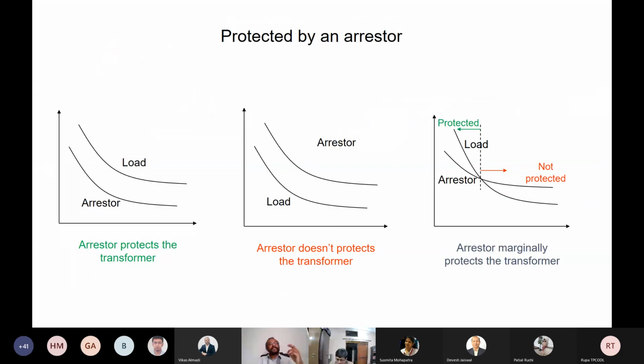And then now say that your load is a transformer, and then you're having a protective device which is a surge arrestor. Now, when you get the VT characteristic of the arrestor and the load, if you see two curves like this, the first one, then your arrestor will protect the transformer because the arrestor will operate before the breakdown happens across the transformer. But if it happens in this way, load has a lower curve than the arrestor, then your load or the transformer is not protected at all.